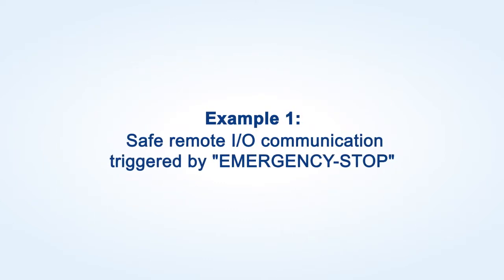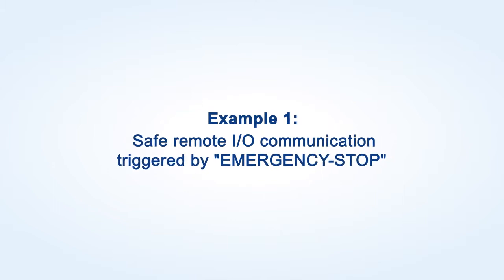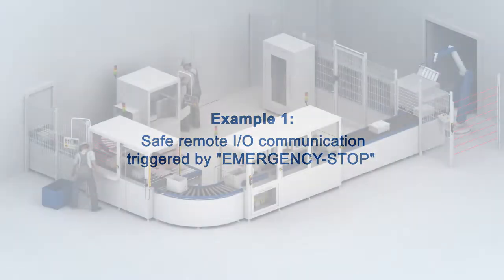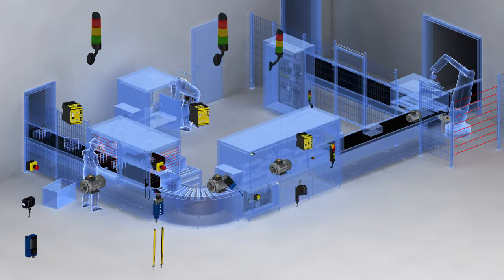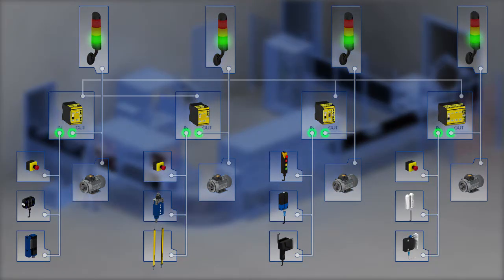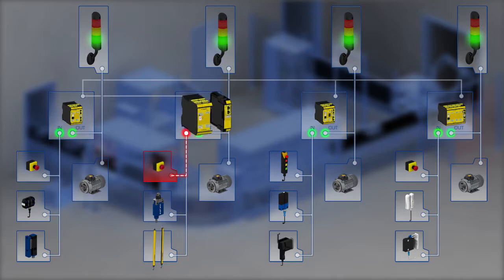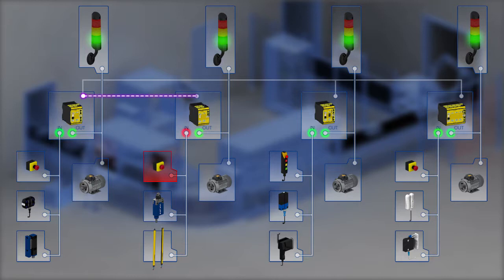Example 1 – Safe remote I/O communication triggered by emergency stop. With the actuation of the emergency stop command in system component 2, the remote I/O module sends a telegram with the information 'emergency stop actuated' to the upstream safety controller. The communication takes place via Ethernet using the internal communication module and the Safe Device-to-Device Communication protocol, SDDC for short.